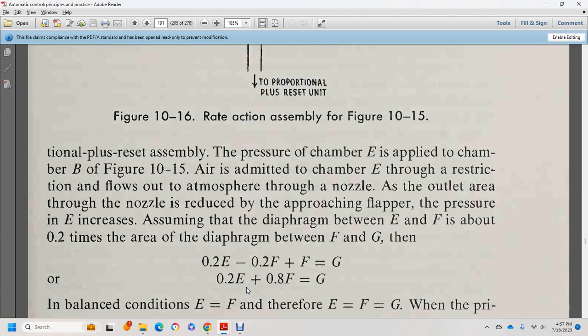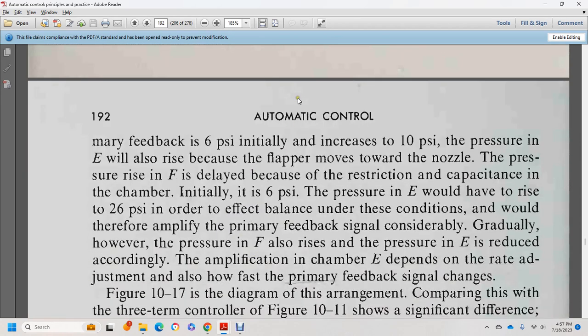The rate unit: air admitted to chamber E flows to atmosphere through a nozzle outlet, approaching the flapper, causing pressure E to increase. The diaphragm between E and F has a ratio of 0.2, and the diaphragm between F and G gives: 0.2E − 0.2F + F = G, or 0.2E + 0.8F = G. At balance, E = F, so E = F = G. When the primary feedback increases to 10 psi, the pressure in E also rises, moving the flapper toward the nozzle and increasing pressure. The delay via the restriction and capacity in chamber F causes initial high pressure E, resulting in amplification of the primary feedback signal.